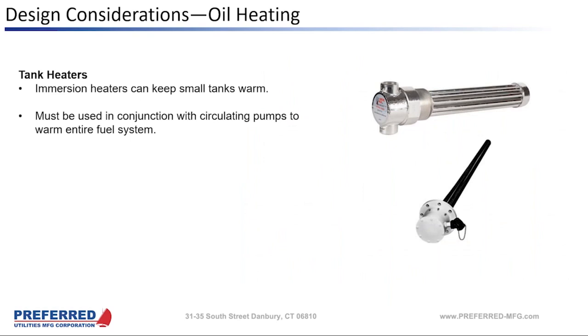We get asked to provide tank heaters a lot, and we don't usually supply them very often. We try and talk engineers out of tank heaters because these immersion heaters can provide BTUs to the oil, but they don't provide any circulation. So unless you've got circulating pumps in the tank or some way of circulating the fuel and heating it, immersion heaters like this are not very effective.